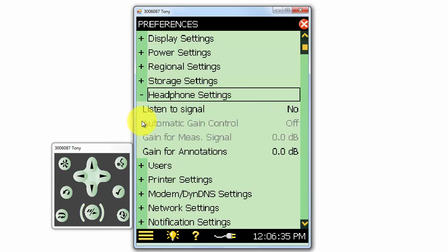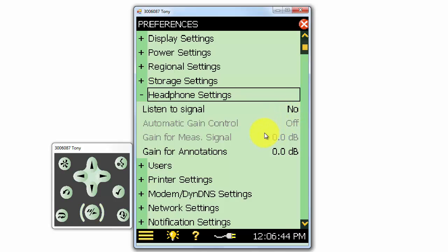Under headphone settings, we can select whether or not we'd like to listen to the microphone or accelerometer signal at the earphone connector on the bottom of the meter. We can also apply some gain to this output.